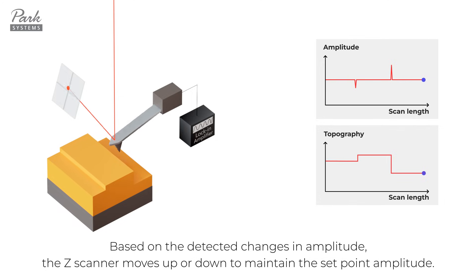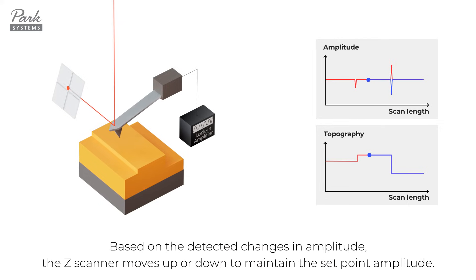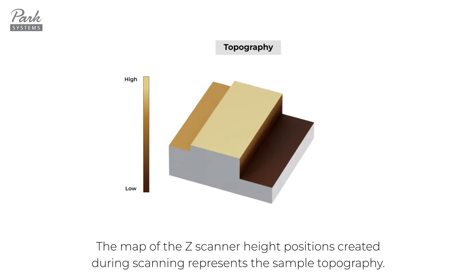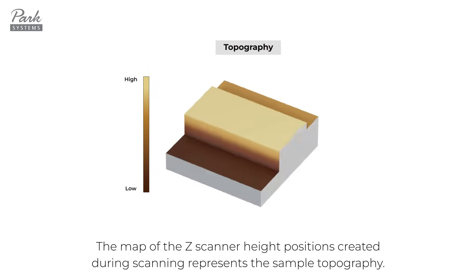Based on the detected changes in amplitude, the Z-scanner moves up or down to maintain the set point amplitude. The map of the Z-scanner height positions created during scanning represents the sample topography.